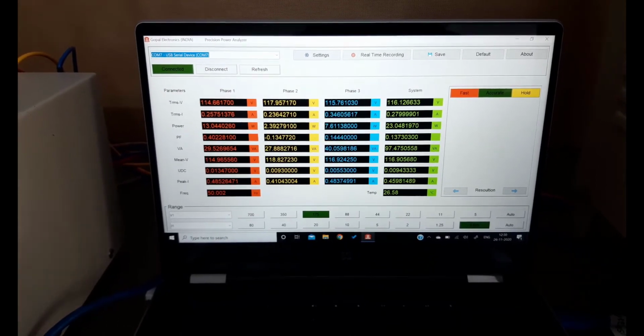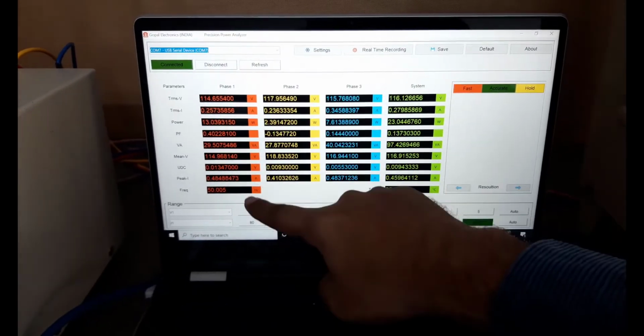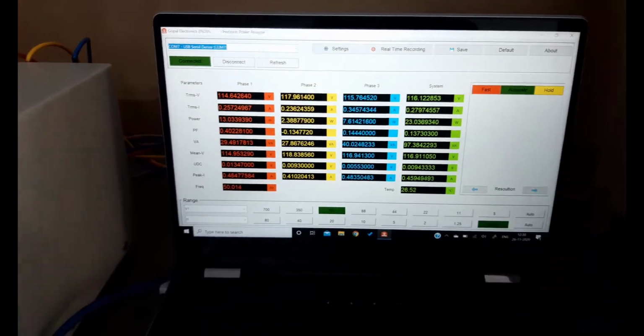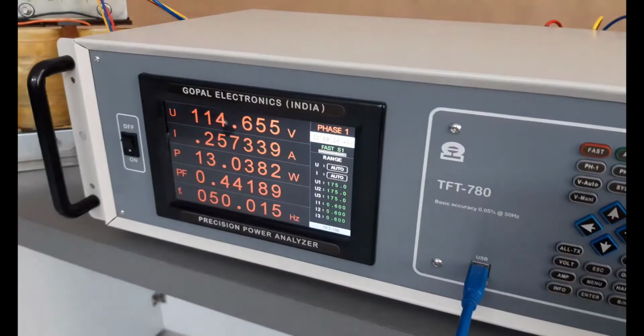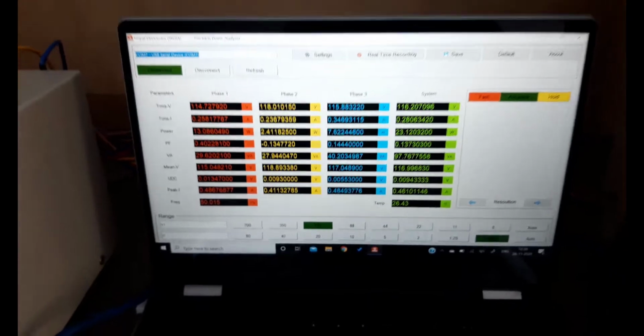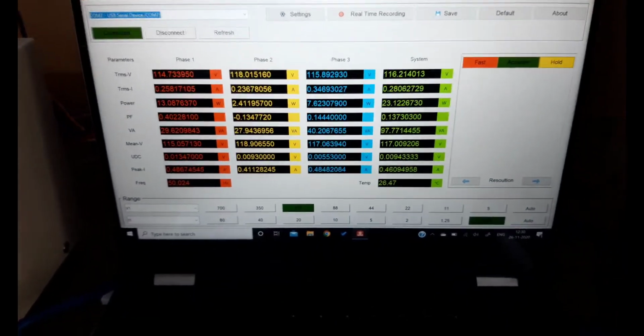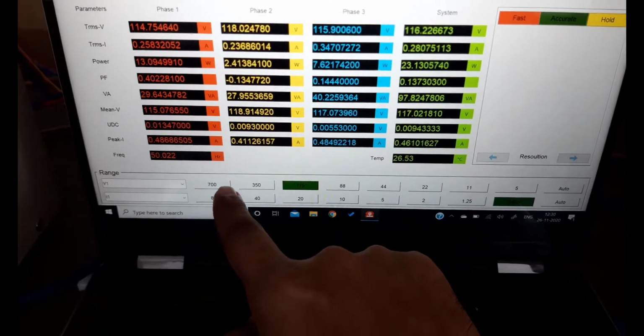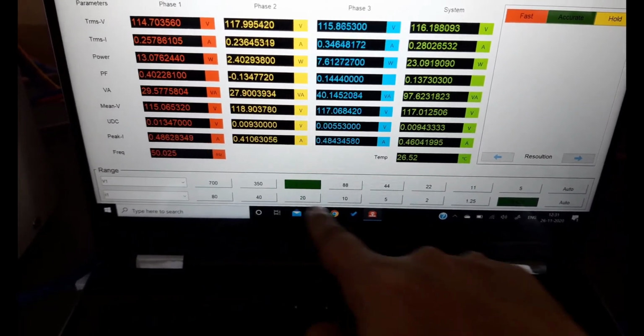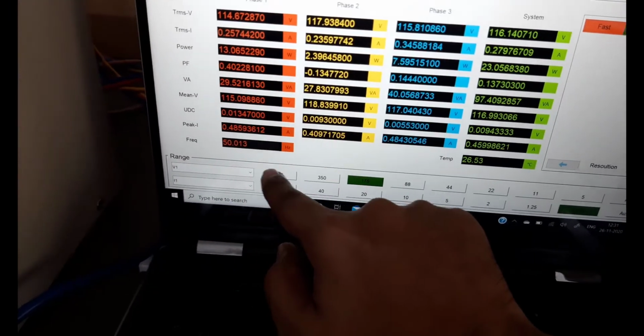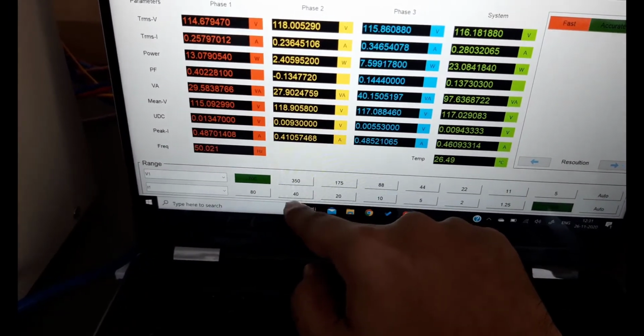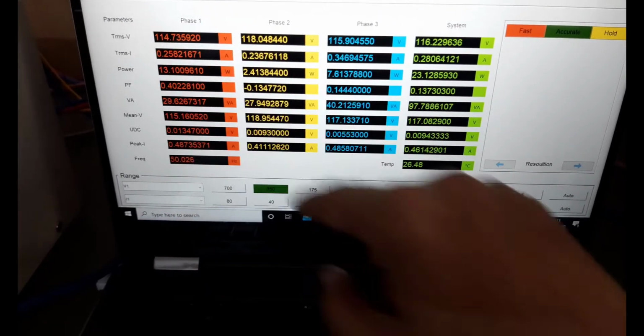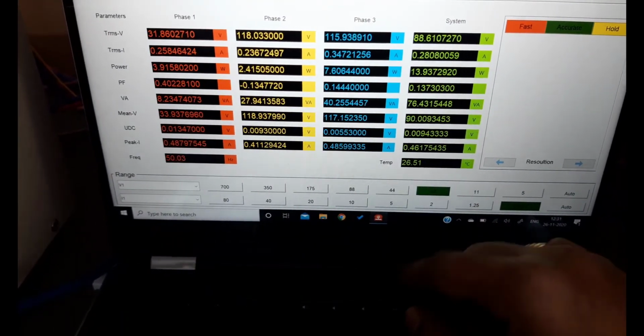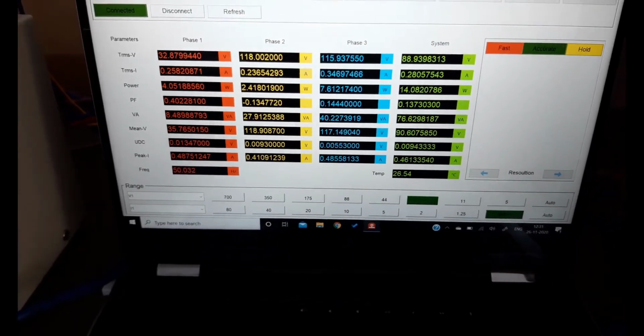Now let's check the software. This is giving instantaneous live values from the power meter. You can see 114 volt, 114 volt, correct? These are the range for voltage and current. You can change range from here, 700 volt, 350 volt. Right now it is 100 volt. Suppose I select a 22 volt range, it will show overload. Right?